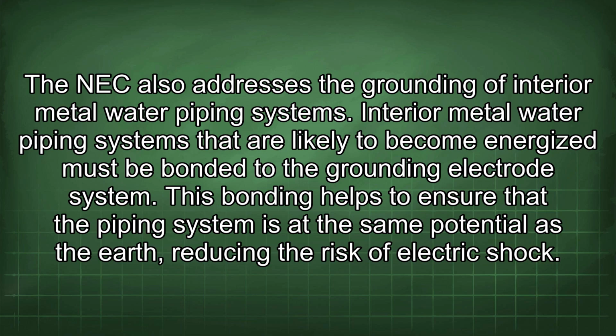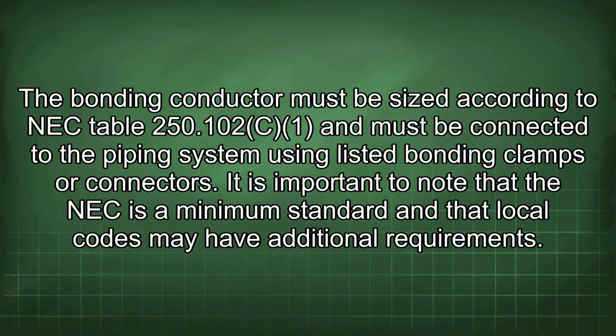The NEC also addresses the grounding of interior metal water piping systems. Interior metal water piping systems that are likely to become energized must be bonded to the grounding electrode system. This bonding helps to ensure that the piping system is at the same potential as the earth, reducing the risk of electric shock. The bonding conductor must be sized according to NEC Table 250.102(C) and must be connected to the piping system using listed bonding clamps or connectors. It is important to note that the NEC is a minimum standard and that local codes may have additional requirements.